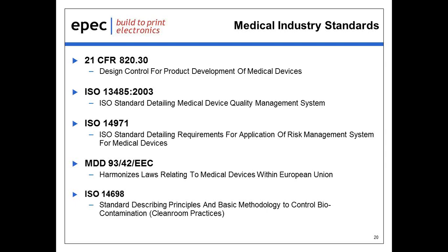There are also standards that harmonize laws relating to medical devices within the EU. Standard ISO 14698 really details how to control biocontaminants in the production of medical devices. And in that standard, it specifies the characteristics of varying levels of clean rooms based around the ultimate use of that medical assembly.